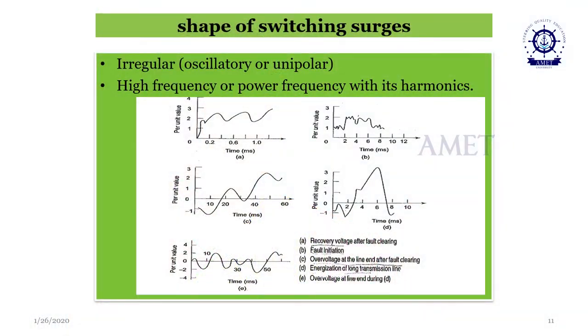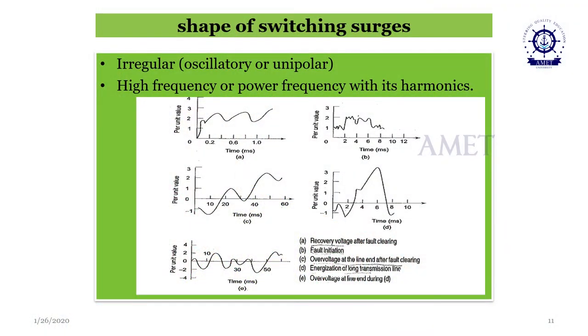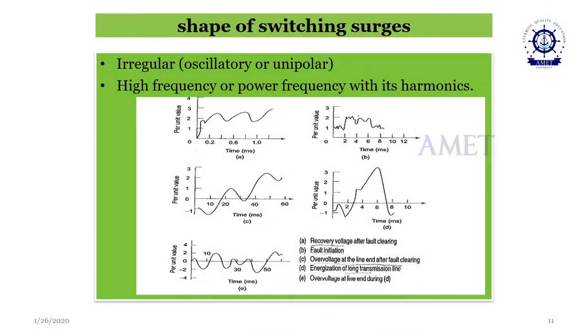You can observe the waveform has no particular shape, and it keeps varying. There is a jerk or a jump, a sudden rise in the peak value of the voltage, and again it diminishes, and again it increases. These are mainly due to sudden actions, say fault clearing, then fault initiation, then over voltage of the line, end of the fault clearing, and then energization of long lines. Energization of a transmission line itself is one type of sudden action. When you suddenly energize an extra high voltage transmission line, it injects switching surges into the system, and that is the D waveform, which represents it very clearly.